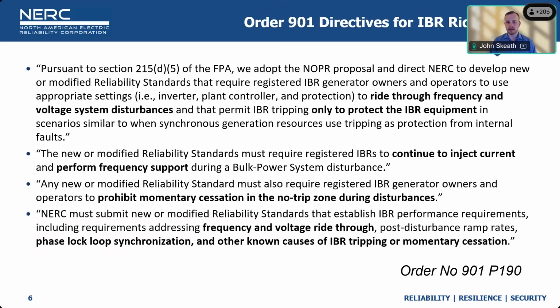I'm not going to read everything that's here on the screen. I'm just going to highlight a few of the surrounding text. This is cited from FERC Order 901, paragraph 190. The first bullet essentially is saying that the registered IBR owners and generator owners and operators are to use the appropriate settings and general plant type coordination, as you can see listed in the various items here, to ride through frequency and voltage system disturbances, with a very small subset of permitted IBR tripping, and that's only to protect the IBR equipment in scenarios similar to synchronous generation resources, such as protection from internal type faults.